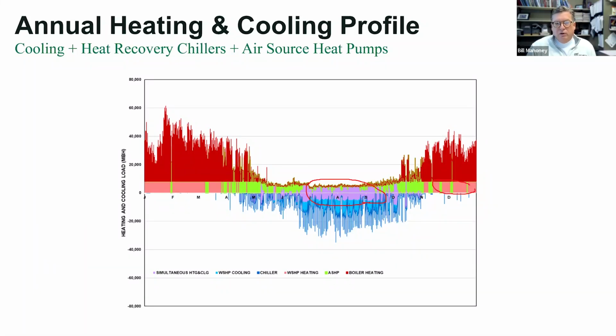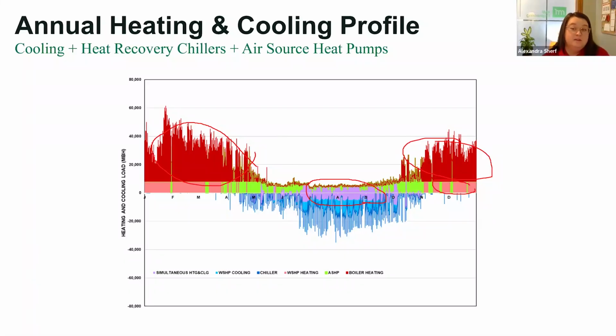As opposed to the efficiency, we have these boilers here in the red. They've got an efficiency, if we're using their steam system, of probably like 80%. So for every BTU we put in, we only get 80% of the BTUs out. So it's really energy-wise; dollars is a different story because the energy costs more for electrical. But as far as energy in versus energy out, you're getting multiples better with these compressorized heat pumps, air source heat pumps, ground water source heat pumps. So it's good to do the simultaneous heating and cooling.